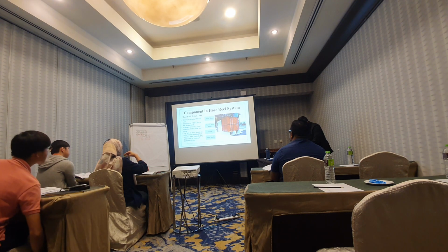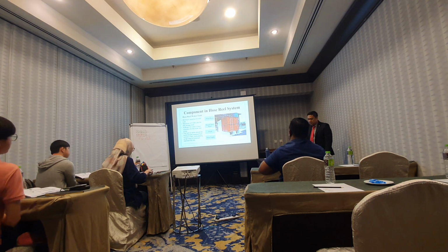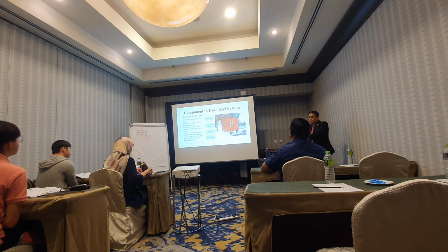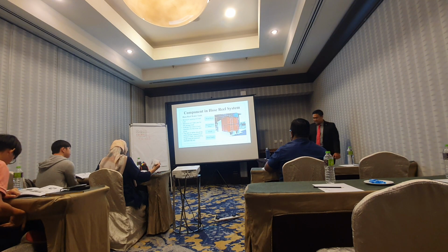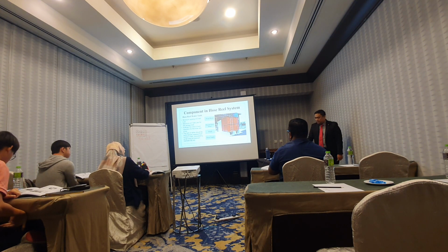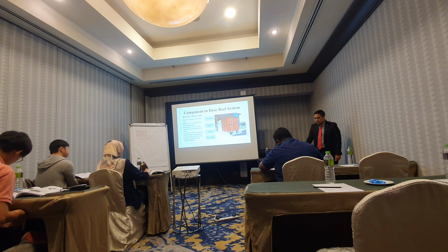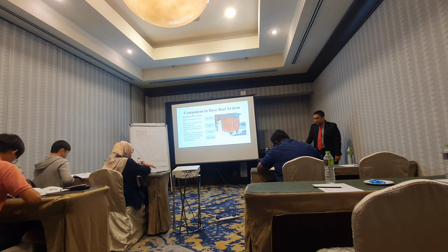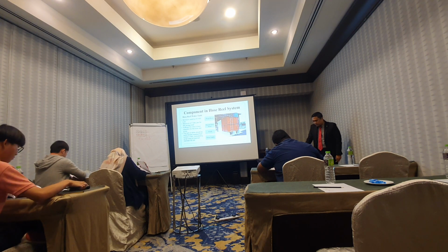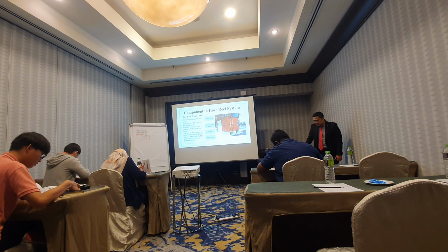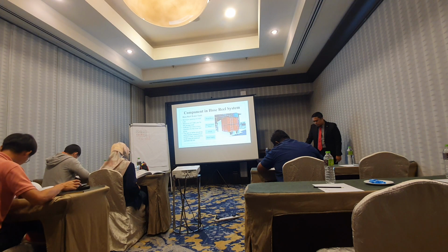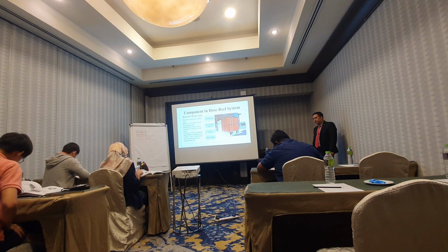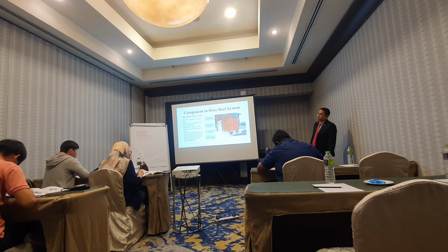Hose reel water tank. This is the latest punya, saya ambil yang latest punya standard. Minimum capacity is 5,400 liter. The maximum is 7,250 liter for the storage tank. Sufficient for 1 hour operation for the hose reel pump. The tank should be automatically supplied from a town main controlled by a ball valve, a minimum diameter 50 mm. Ini semua dari standard.